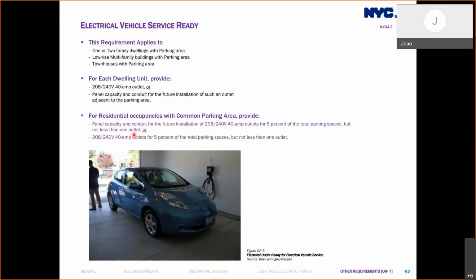So let's say this common parking area has 30 parking spaces. Then 5% of the 30 parking spaces would be 1.5, right? So is it 1.5 or do we compare 1.5 or 1? 1.5 is bigger. So this 30 parking spot communal or common parking area is required to have at least 2 outlets or panel capacity and conduit for the future installation of 208/240 volt 40 amp outlets.